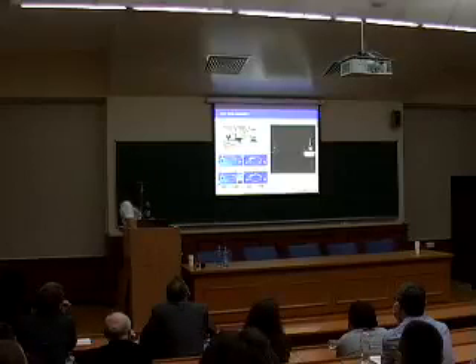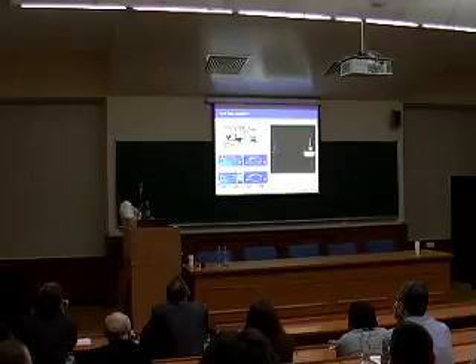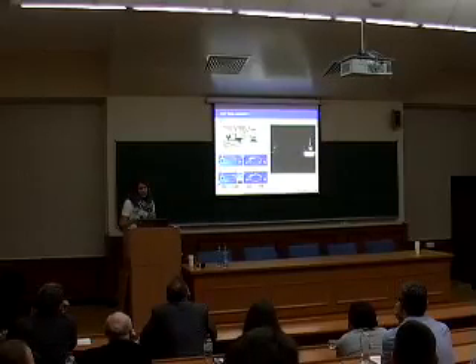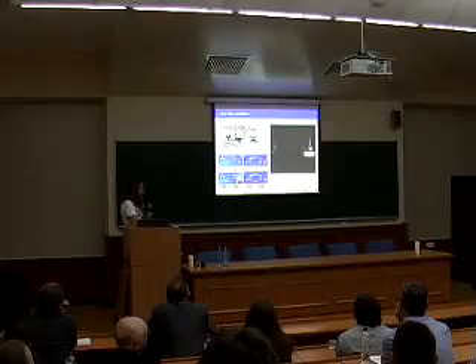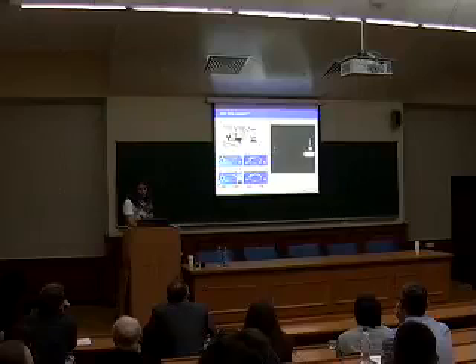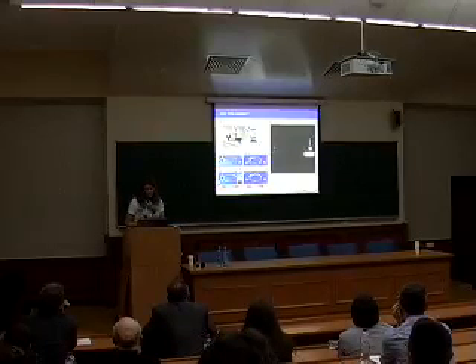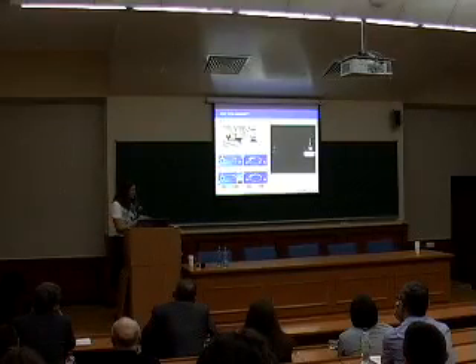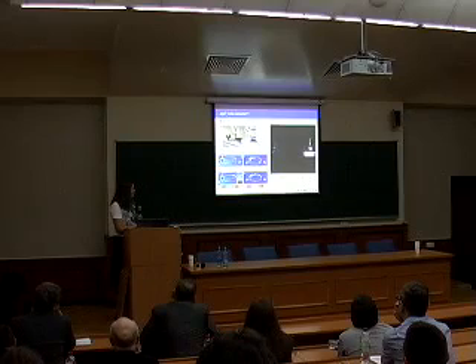Once the device is placed under one of the arms, as you can see, it attracts all the B1 plus field in close proximity to it. Therefore, it really targets the excitation field of the birdcage coil to the target, in that sense, the arm, while SAR values stay comparable. So it not only increases the receive efficiency of the birdcage coil, it also increases its transmit efficiency, and actually achieves 3 times higher B1 plus values when this material is present under the arm than in the case of the standard examination.